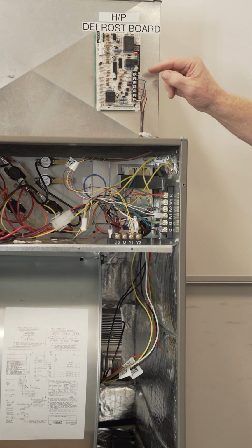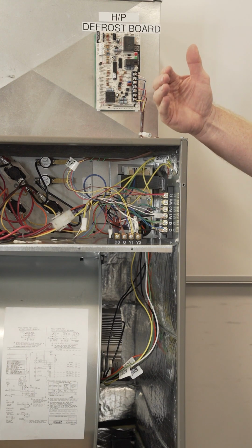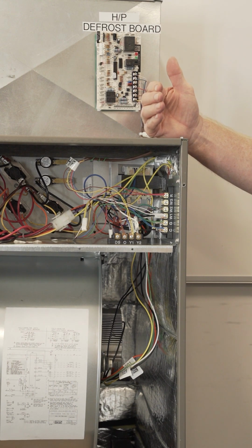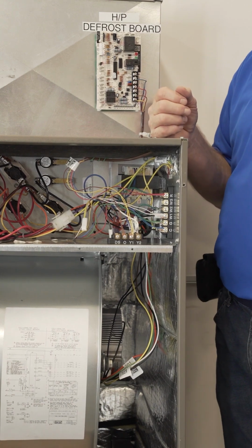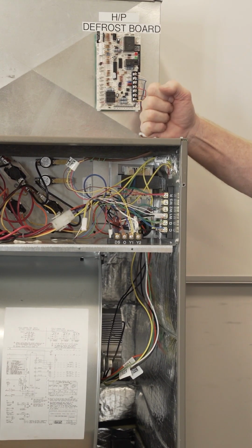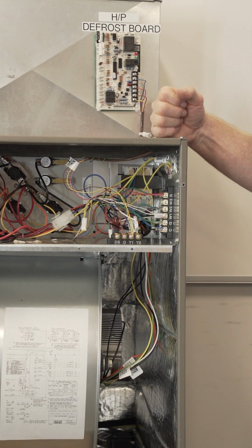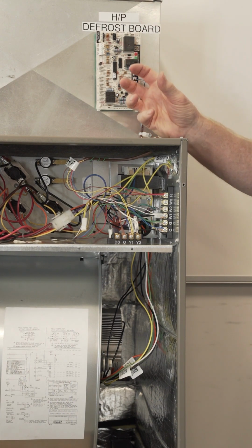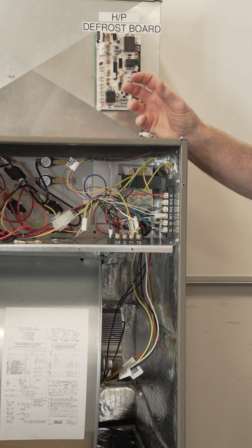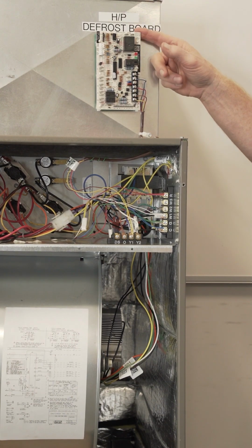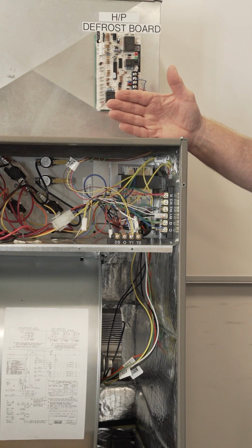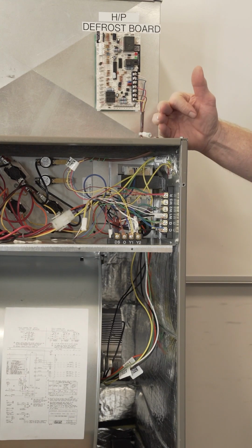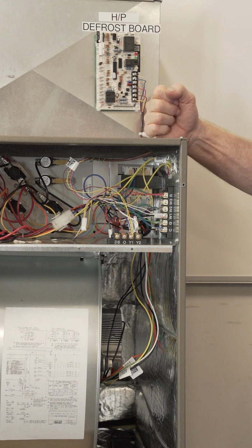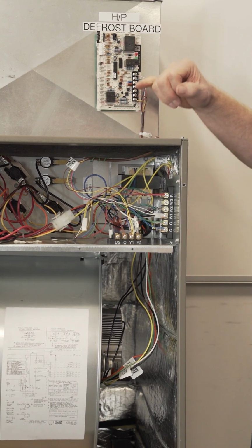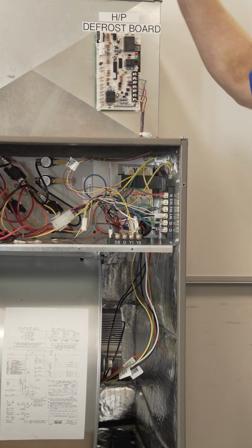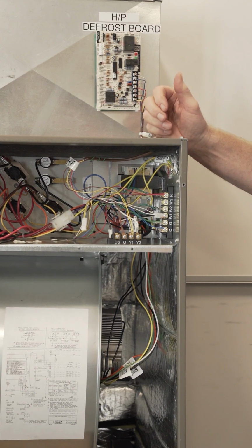And then you have white up here, W1, which is our auxiliary heat. That auxiliary heat comes on if it's too cold and the heat pump can't meet the demand, or the thermostat gets cranked up a lot higher than what it is in the house, or primarily when the outdoor unit goes into defrost. The air conditioning comes on, so instead of blowing too much cold air on the homeowner, we turn on those strip heaters through W1, through the defrost board.